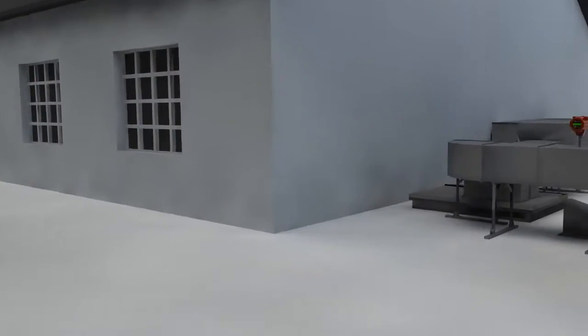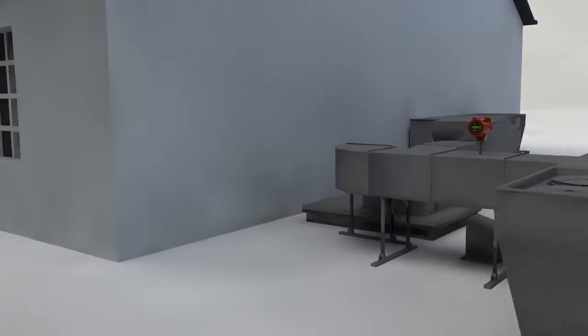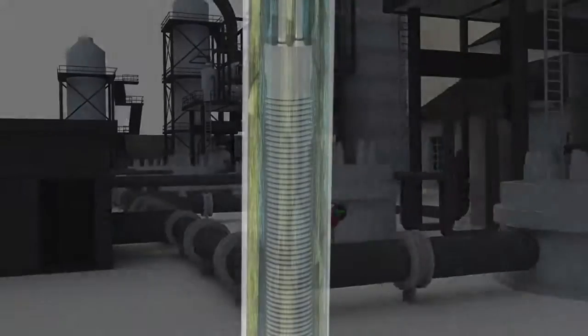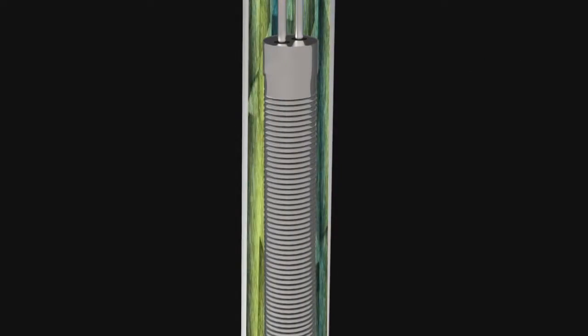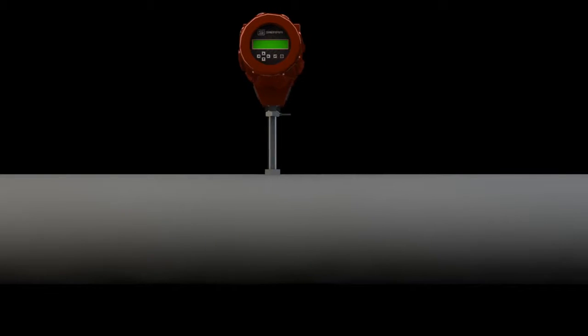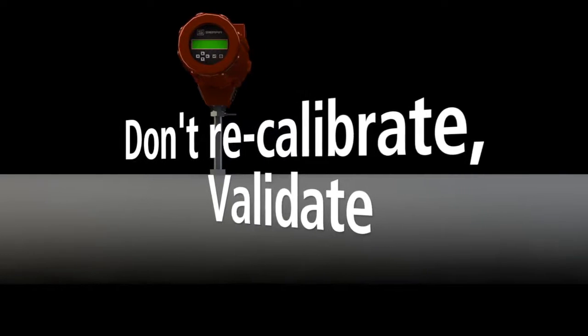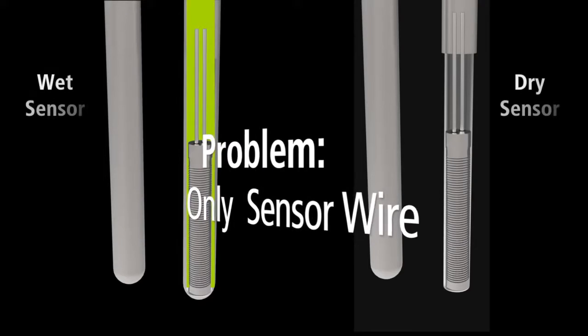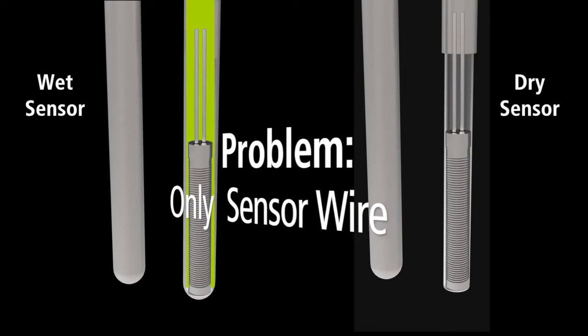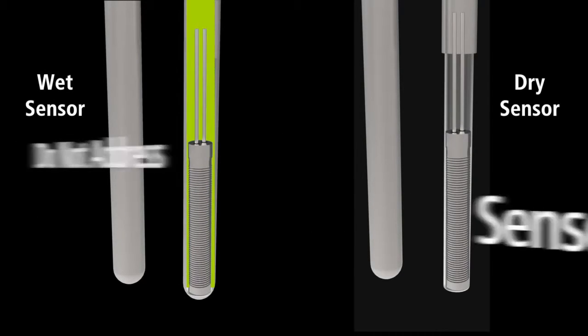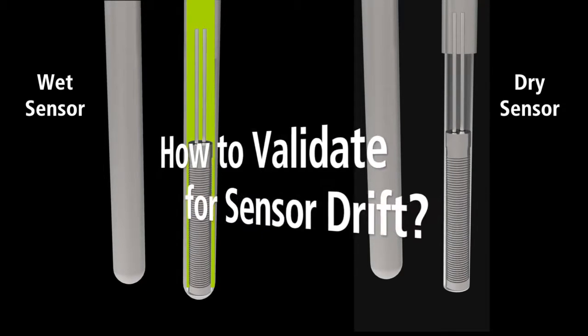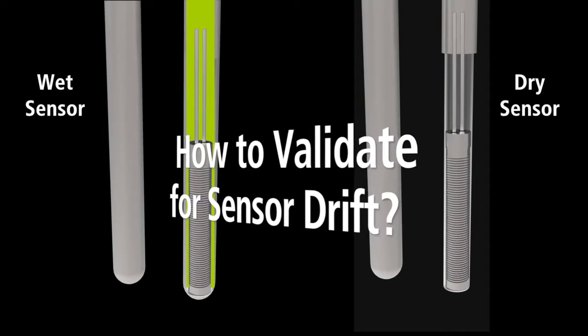So, when evaluating thermal mass flow meters for in situ calibration validation capability, be aware that sensor drift will create false positives, reducing the reliability of the validation. Sierra's motto has always been, don't recalibrate, validate. Be careful. The problem with in situ validation methods is that they only measure the characteristics of the internal sensor windings and do not address sensor drift. The big question is, how can you validate a sensor that will drift out of spec due to the very nature of its mechanical design?